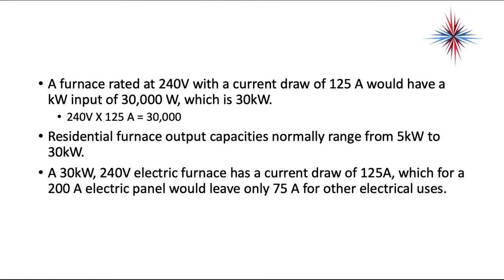So electric heat, what we're trying to tell you, has a very high current draw, and you have to be very careful about the power supplies that they're attached to. We must remember that all electrical work must conform to the requirements of local codes and ordinances, as well as NFPA 70, which is the National Electrical Code, current edition, or whatever edition is in effect for the area of jurisdiction.